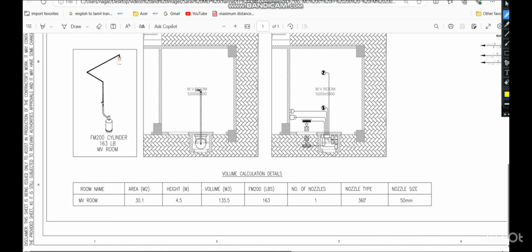And the next one is the FM 200, because in this project the client wants to use the FM 200. We have multiple clean agent systems like FM 200 and Novec systems. So we are using FM 200 for this project. So this is an MV room. MV means medium voltage electrical room. As per the area requirement, the specialist has recommended only one cylinder, sufficient for this small room. So the cylinder with the capacity 163 pounds we are using, and only one nozzle can cover this full area as per the requirement. So we are using one nozzle.